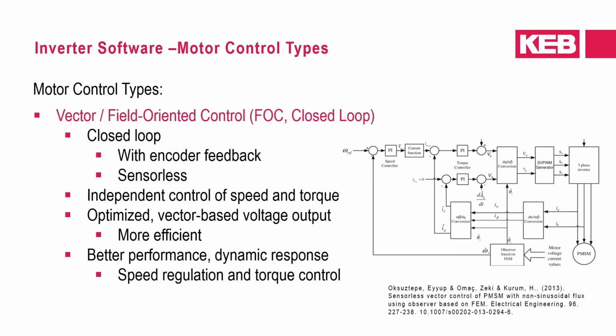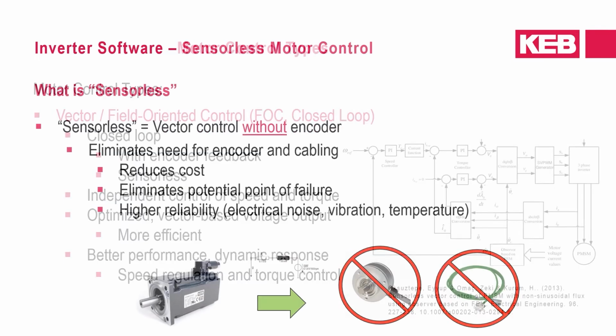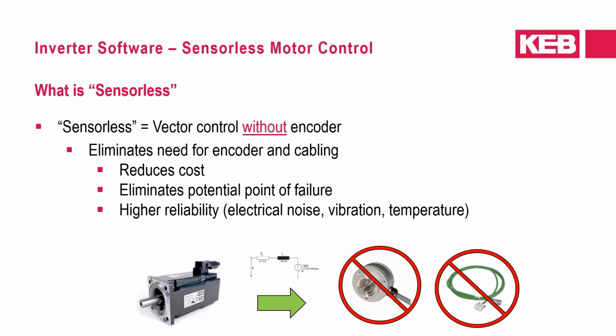On the other hand, there's vector or field-oriented control. This type of control is closed loop and either utilizes encoder feedback or sensorless algorithms. With vector control, there's independent control of both torque and speed. Additionally, the voltage output is optimized based on vector calculations and therefore operates more efficiently according to the actual load requirements. Most notably, though, is that closed-loop systems provide far better speed regulation and torque control, which allow for higher performance and dynamic response. Coming back to the question of what is sensorless, sensorless means vector control without encoder feedback.